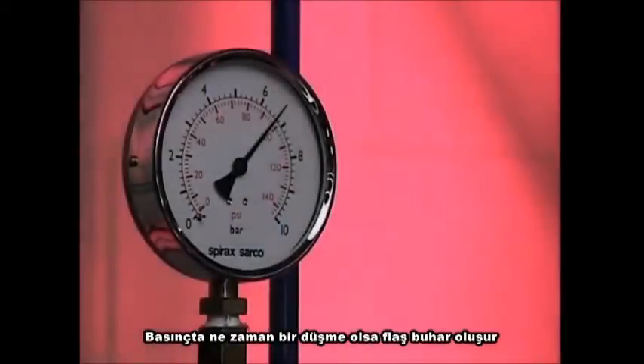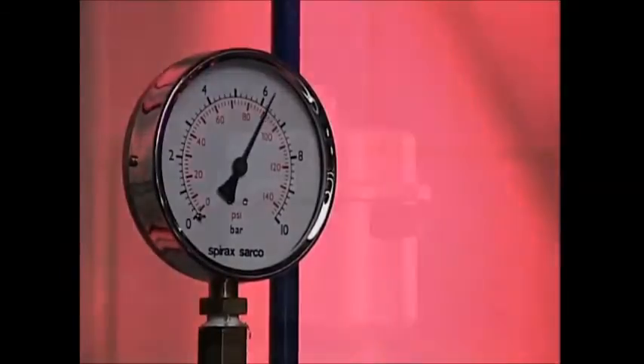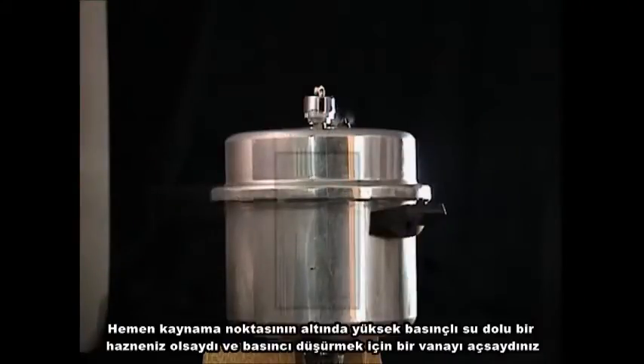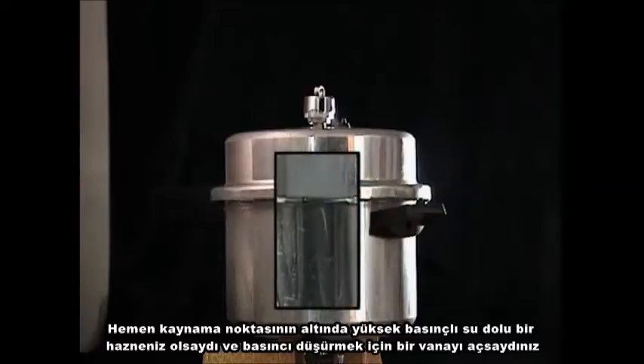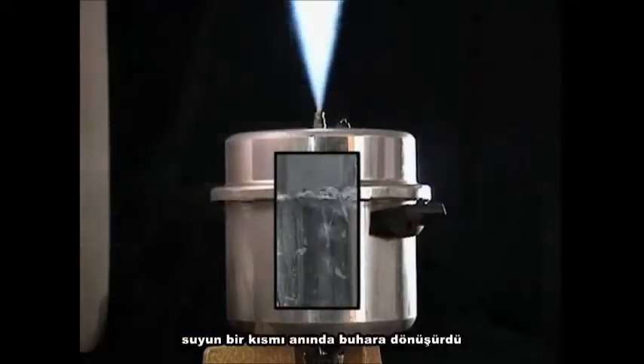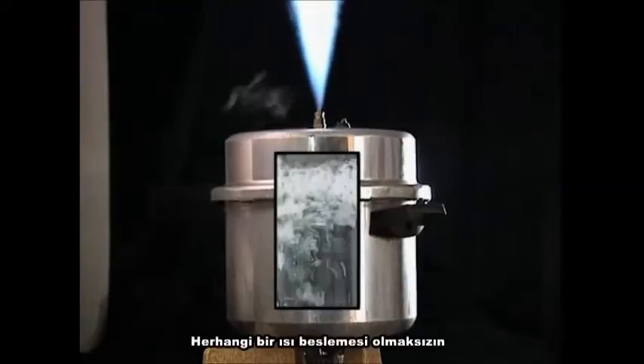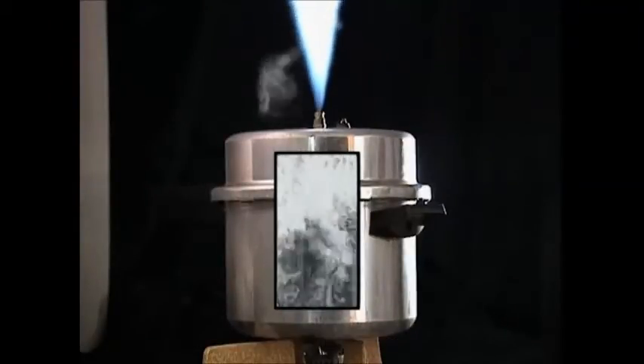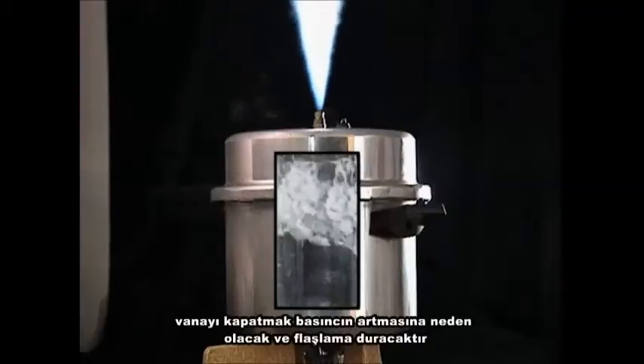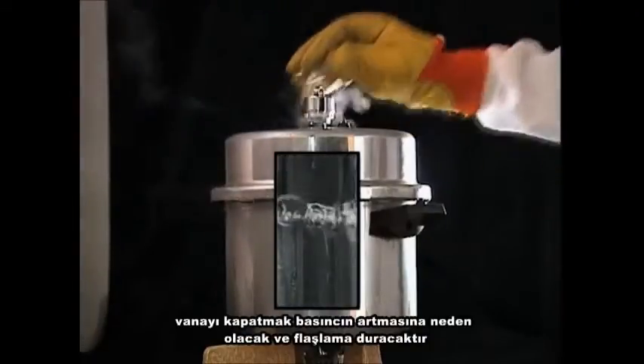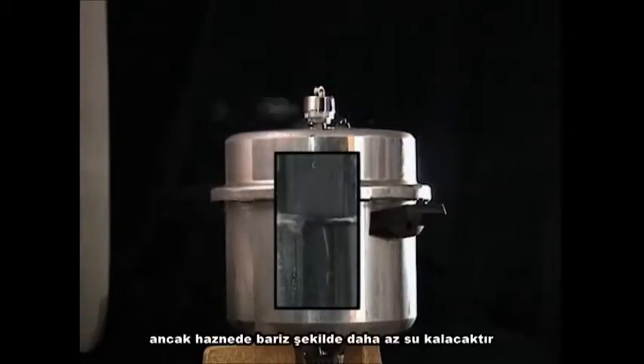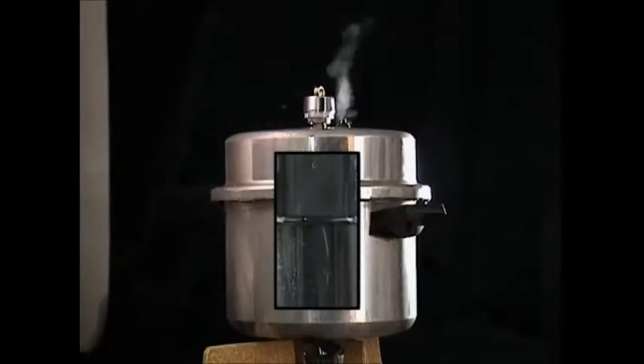Flash steam occurs whenever there is a lowering of pressure. If you had a vessel containing high-pressure water just below its boiling point and opened a valve to lower the pressure, some of the water would spontaneously change to steam, without any heat being supplied. Closing the valve would enable the pressure to build up and the flashing would stop, but there would obviously be less water left in the vessel.